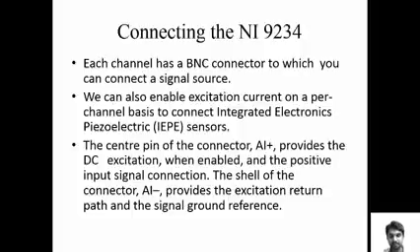As I already showed, the center pin AI plus provides the DC excitation when enabled and the positive input signal connection. The shell of the connector is the negative around the positive signal that provides the excitation return path and the signal ground reference.